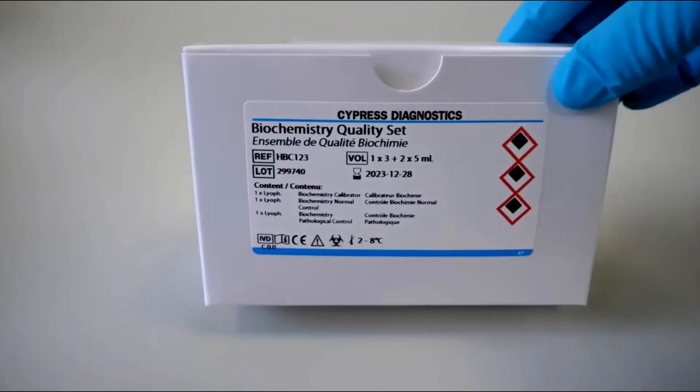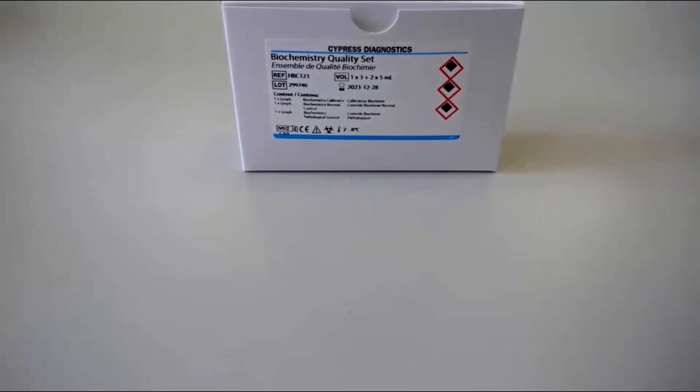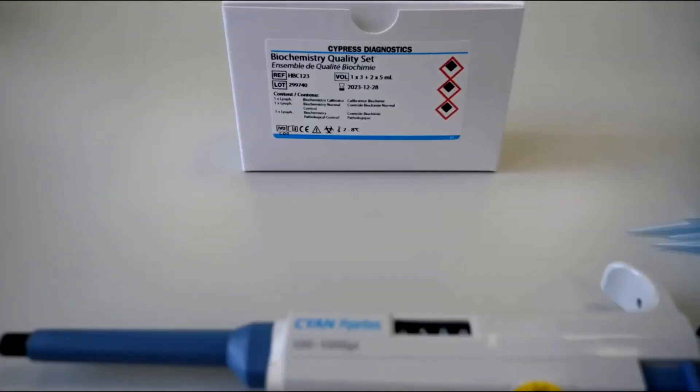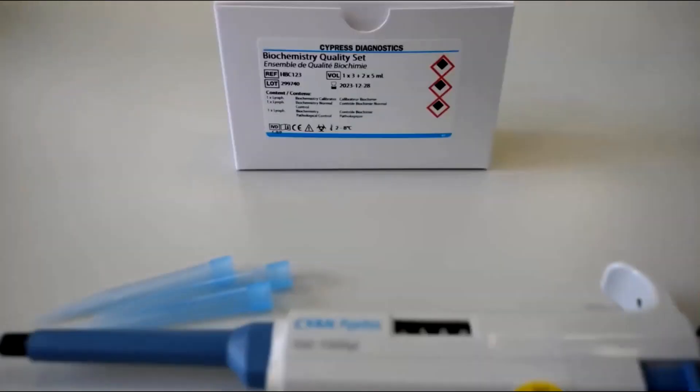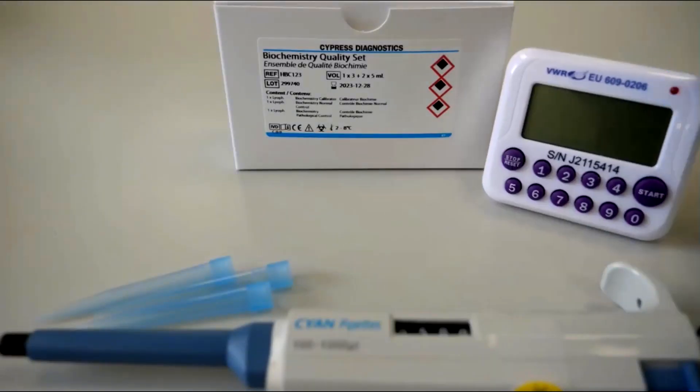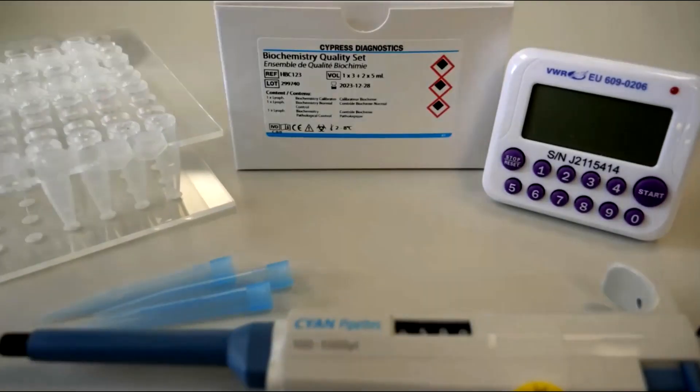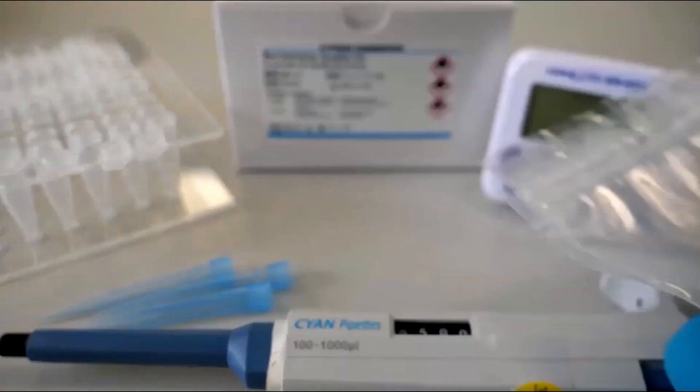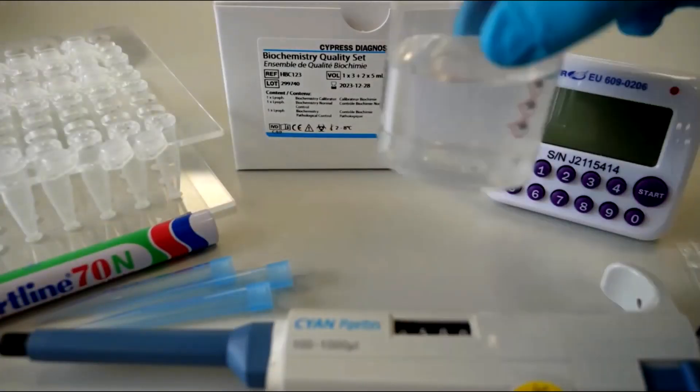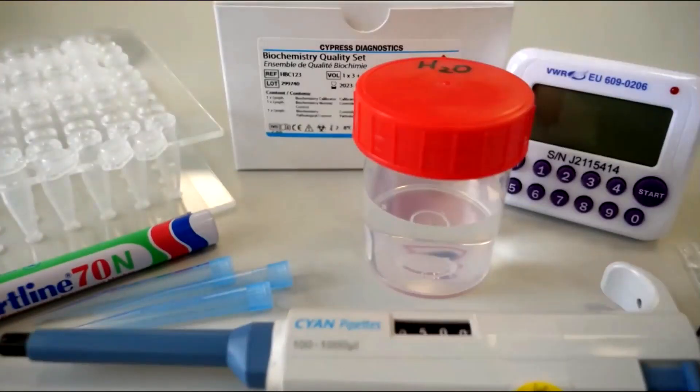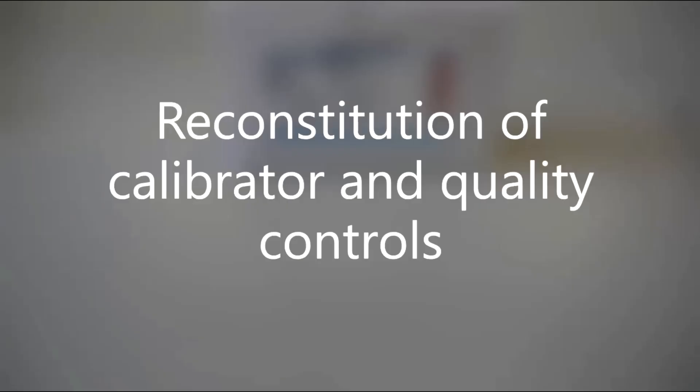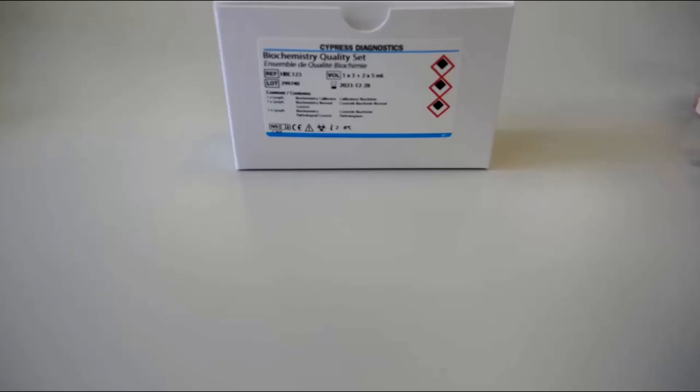For this procedure you will need the Cypress Diagnostics biochemistry calibrator and quality controls, an accurate volumetric pipette, a timer, tubes with caps suited for storage in a freezer, transparent Ziploc bags, a marker and at least 15 milliliters of distilled water.